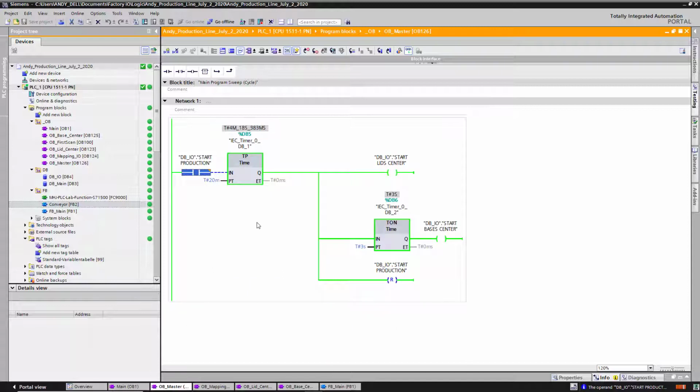And the master one, you already saw this one. When I activate this bit, I get a pulse timer. As you can see, the bit is no longer activated, but the pulse timer is running. This is the beauty of this instruction. It's called the pulse timer. I only need one activation, and then the pulse timer keeps running for 20 minutes. Then, once that 20 minutes is over, this block of code is deactivated.